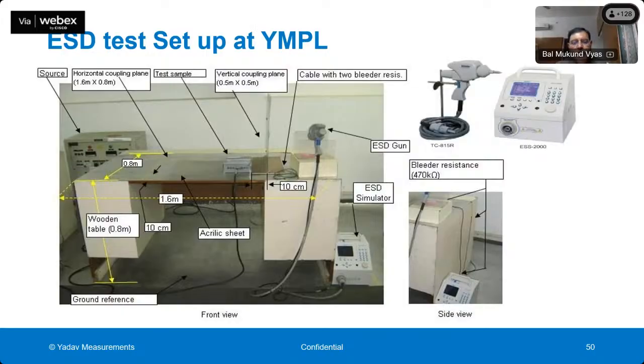And also when this electrostatic discharge happens, the heavy current will also flow, and because the current is very high, it can be a few kiloamperes. This current will generate a magnetic field, a high magnetic field, and the meter should not get affected because of this magnetic field.